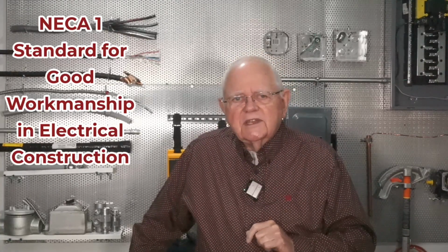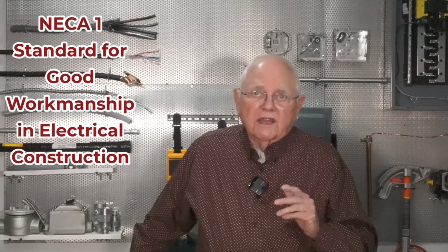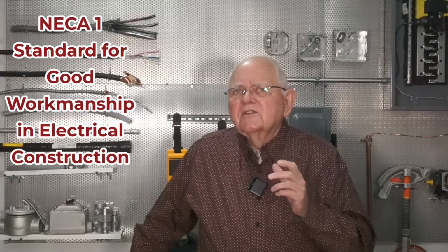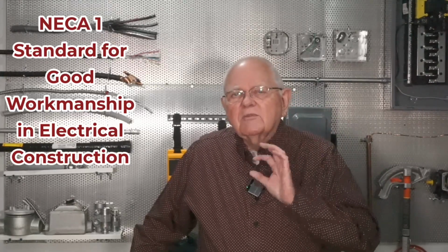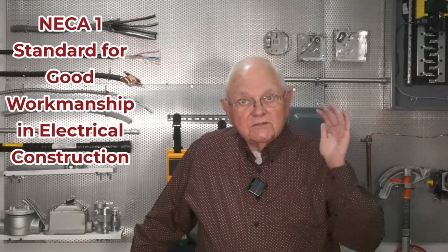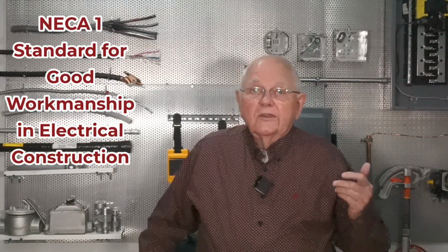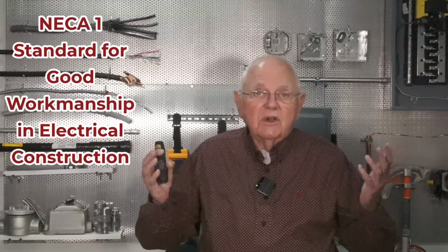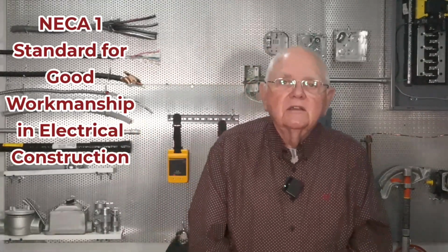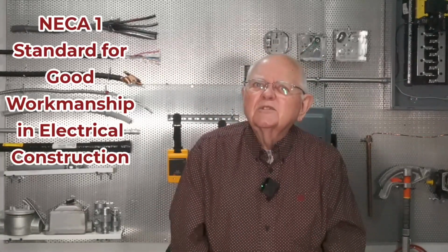So for instance, at a nuclear facility, we had a warehouse where we stored the extra motors that we might need. And there was a requirement that every so often you had to go around in certain size motors and on up, right? You have to rotate that shaft 1 1/4 turns. Because if that shaft just sits there, maybe for years on end before that motor is installed, you're going to have bearing issues, you're going to have some possible shaft warpage and things like that. Not perceptible to the human eye, but it could be there and cause you problems.